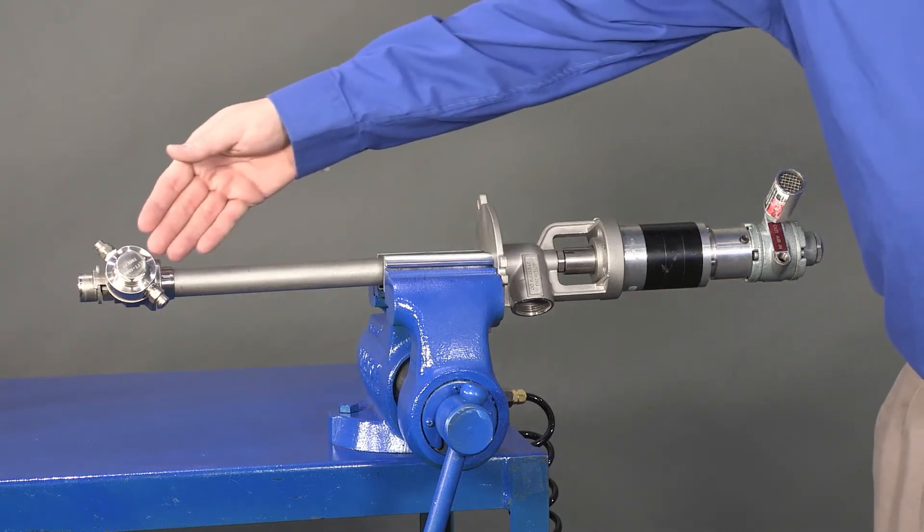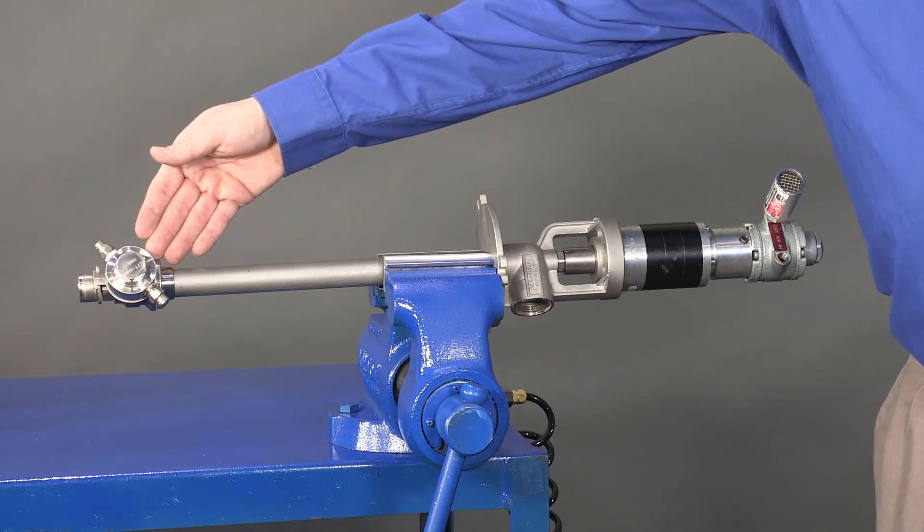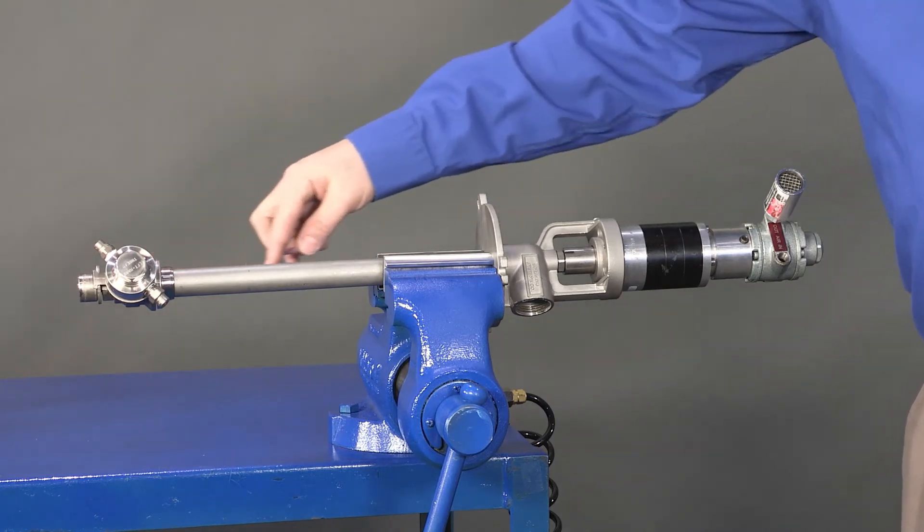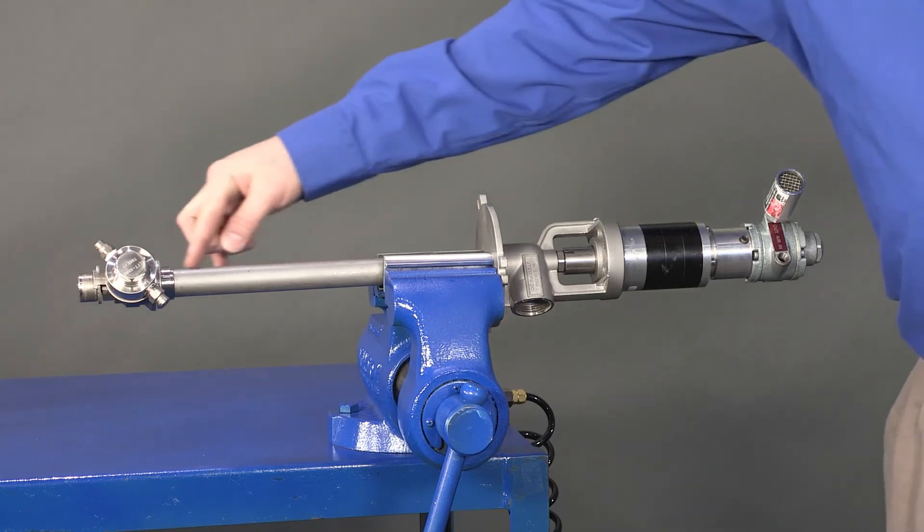Check for obstructions on the gears and nozzle hub that could prevent rotation. Check for bends in the extension tube. Clean off any product residue as necessary.